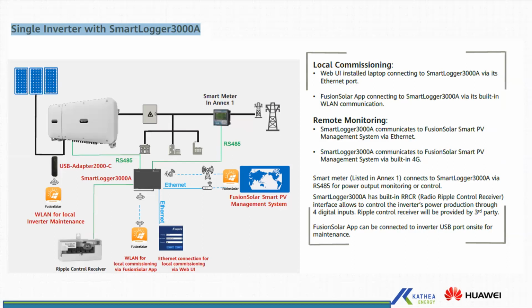So if your meter is not compatible with the inverter, or your plant size or mains incomer is way bigger than 170 kilowatt, then you would need a smart logger. You wire your meter to the smart logger through RS-485, and you wire the inverter to the smart logger through RS-485 as well. Then the smart logger is responsible for connecting to FusionSolar for remote monitoring and control. You can connect to the internet through an Ethernet cable, or you can install a 4G dongle. And for local commissioning and maintenance, you can use the SUN2000 adapter, which is a USB device connected directly to the inverter, and then you can access the inverter for local maintenance.